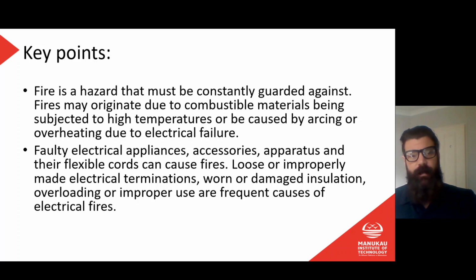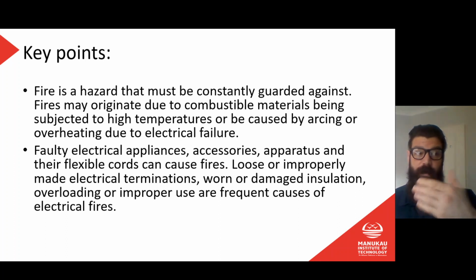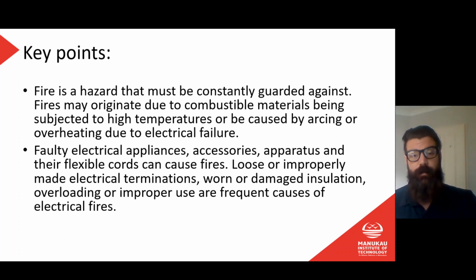So if we have bad connections, if you have a connection inside a light switch or a socket that's only hanging on by one thread of your copper wire, then that little single thread is going to be carrying the whole current for the circuit, and you're likely to get hotspots or high temperatures where that tiny little thread of cable is, and that's something that can cause a fire.